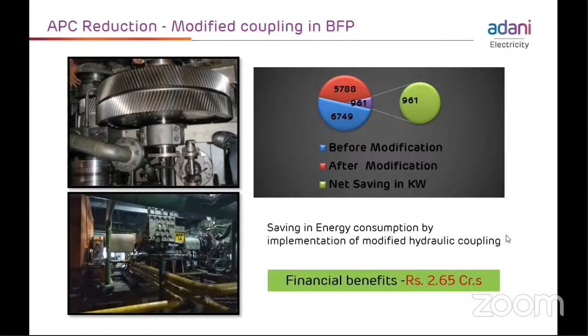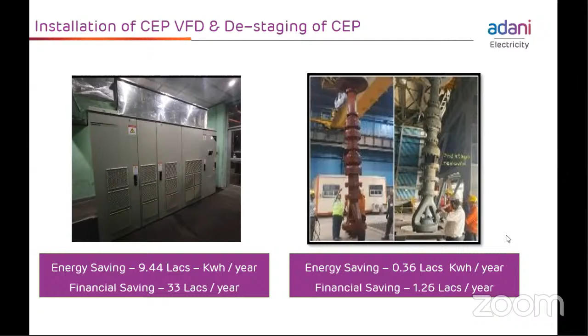This is the installation of VFD, the variable frequency drive, for the condenser extraction pump. And we have also de-staged one of the impellers of the CEP, that is the standby CEP. Because of this, energy saving is happening in both our units. We have reduced the auxiliary power consumption by installation of variable frequency drives to the various auxiliaries in the plant. And over the period, we have been able to save this many million units of electrical energy.